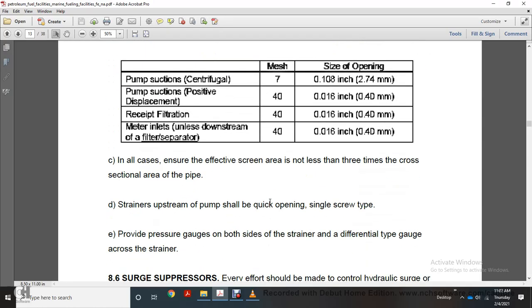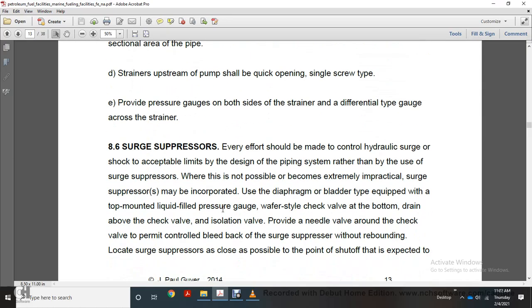In all cases, ensure the effective screen area is not less than 3 times the cross-sectional area of the pipe. Strainers upstream should be quick opening with a single screw. Pipe a differential pressure gauge across the strainer.